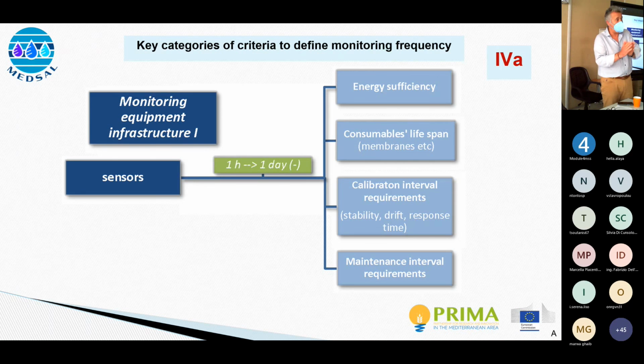One is the drifting of the sensor, which relates to calibration intervals and cannot be overcome. The other is the lifespan of the sensor - the more frequently you monitor, the more you wear the sensor, bringing it closer to the end of its life, particularly for pH or ORP sensors. So you need to be careful how frequently you monitor, because you don't want to ruin your sensors before their time.